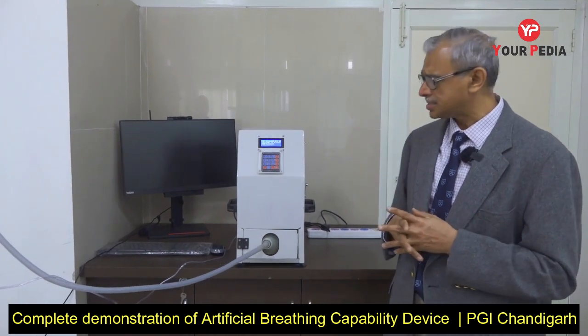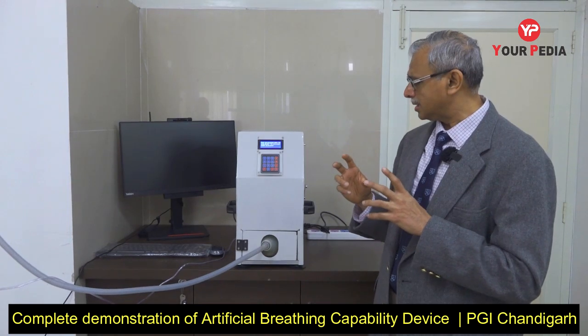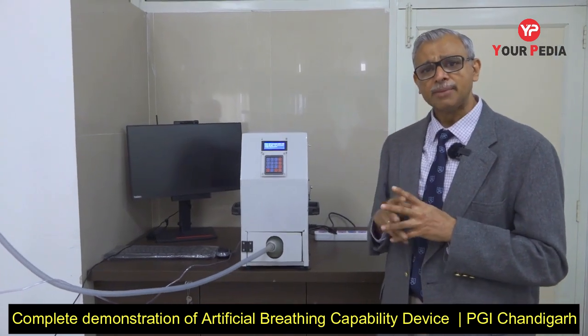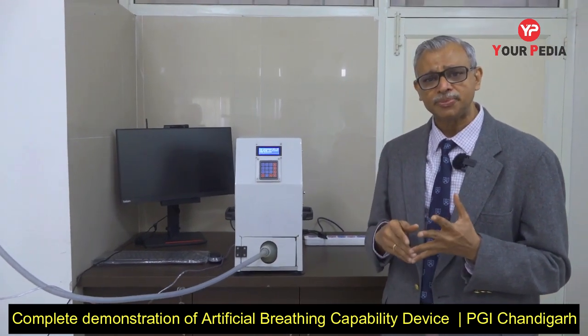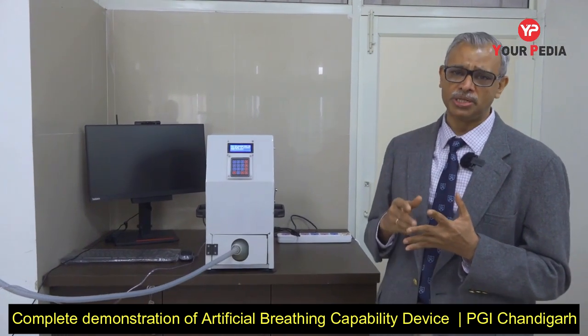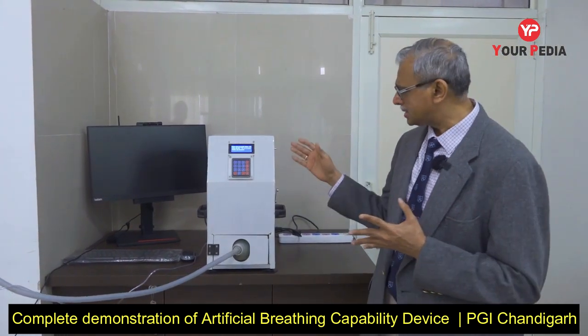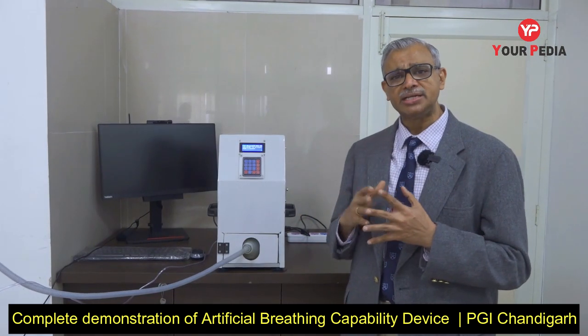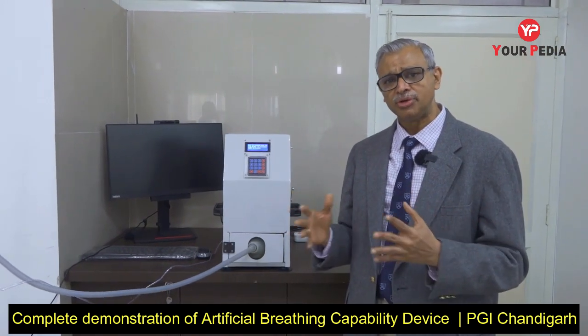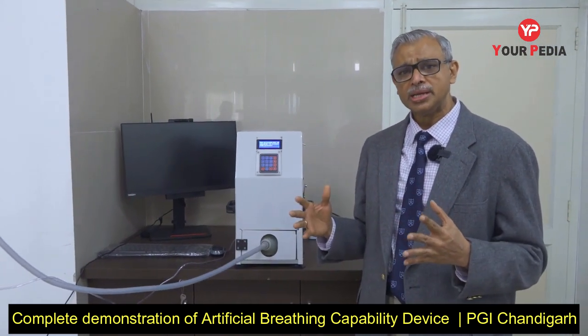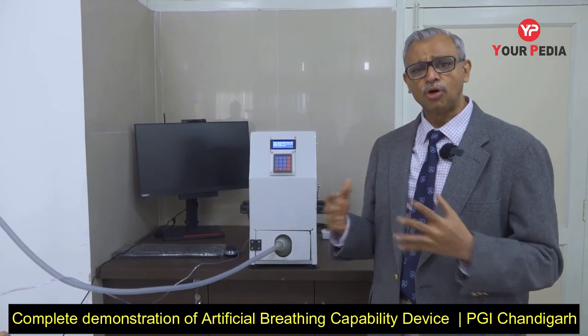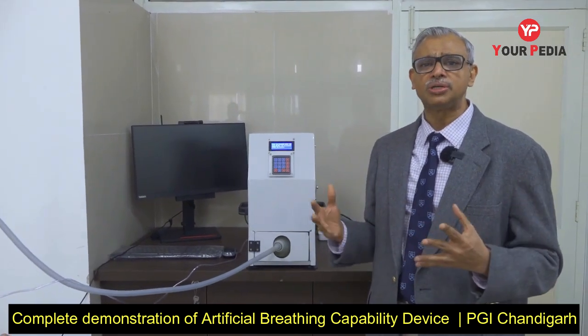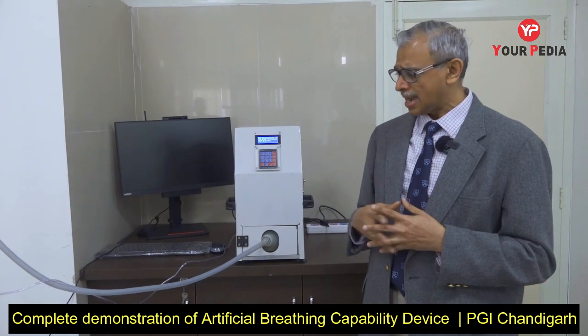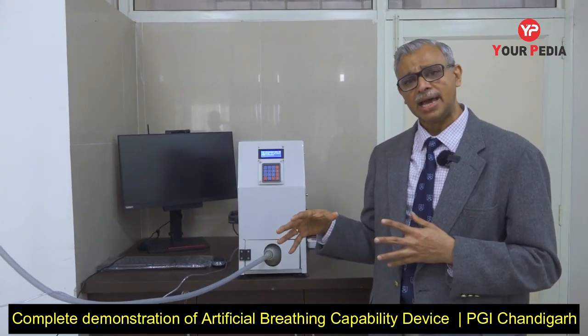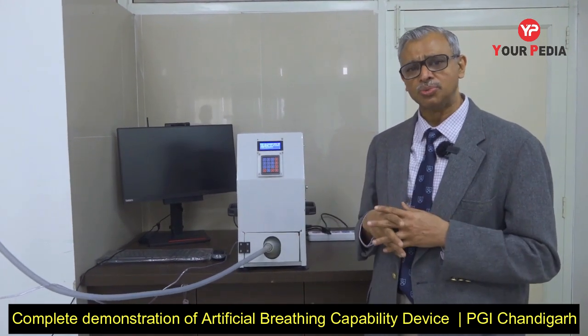We then tested this on a virtual instrument laboratory by which we could test for reliability, robustness, and also precision. We are very keen that these devices should not have any drift. So when we set pressure and we use it over a long period of time, the pressure should not change, the volume should not change, there should be no drift in the recorded parameters. And we took a year of testing in the lab just to make sure that all of this worked.